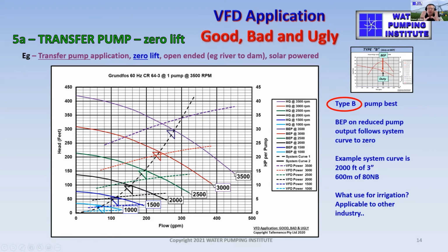So you can see that's the absolute perfect application for a VFD, and you'll find a lot of the big savings, and Roger alluded to those big savings, occur in industry where you have a zero lift at zero flow, and these situations don't exist in irrigation. Okay, so this is a particularly interesting one. It's just a transfer pump, and you can liken it to a lot of the applications in industry. When I say industry, I mean other than the irrigation industry. So in this particular case, a type B pump, where the duty point is right on the best efficiency, is the perfect type of pump to have.